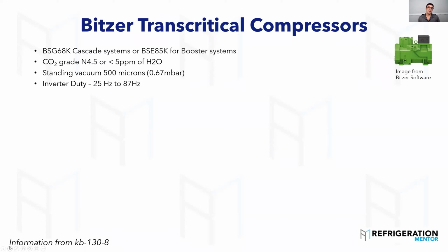Inverter duty. So you have to take a quick, deeper look at this. They can go from 25 hertz to 87 hertz, but it all depends on the compressor. Some will not go down to 25, some will not go up to 87. So you really need to get into 130.8 and look at that specific Bitzer model number you have when you're setting up a VFD. If you do not know how to set up a variable speed or inverter on a compressor, you need to start learning this stuff, because it's happening.